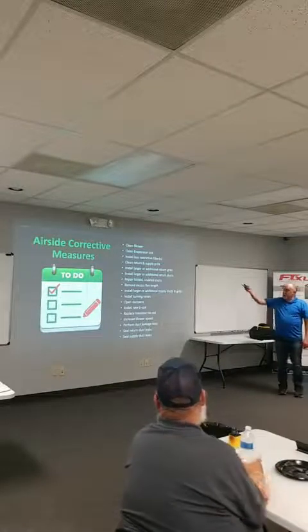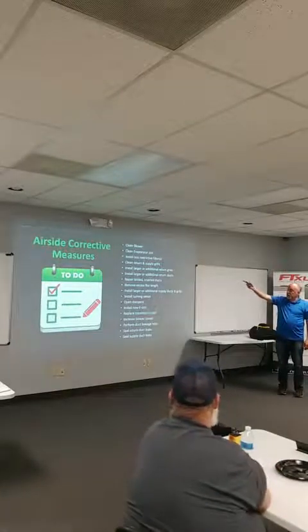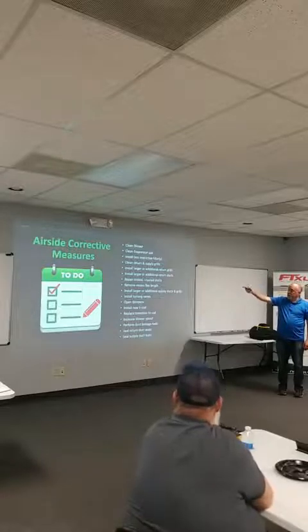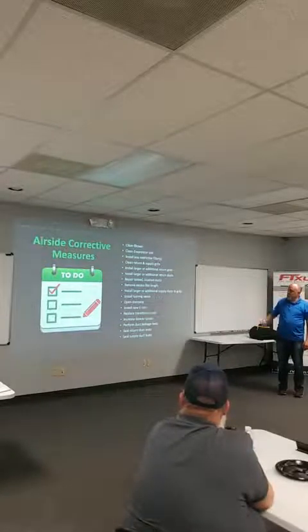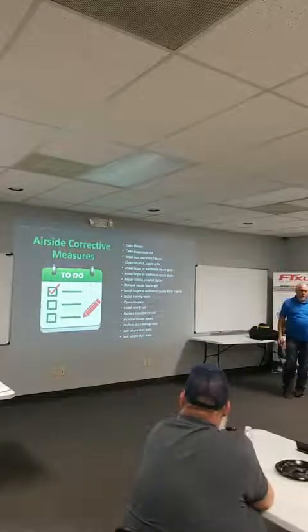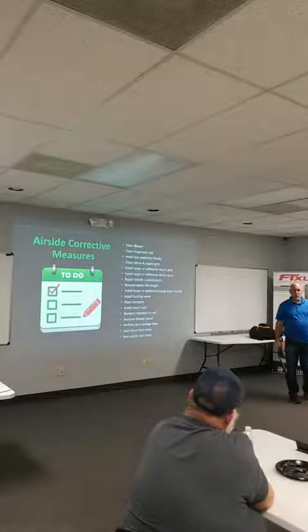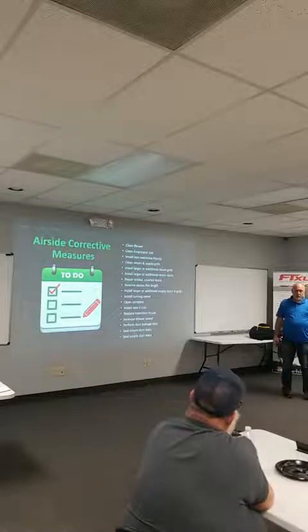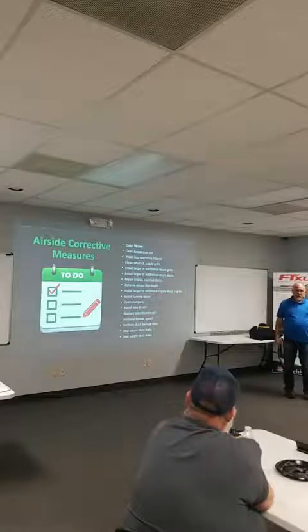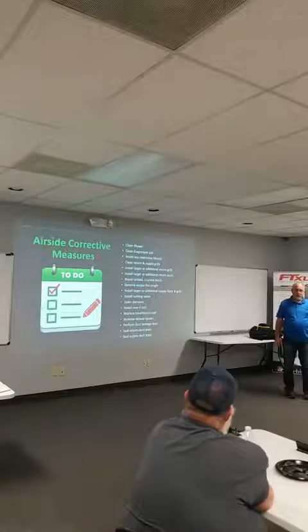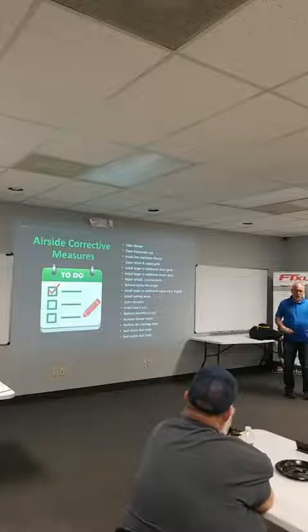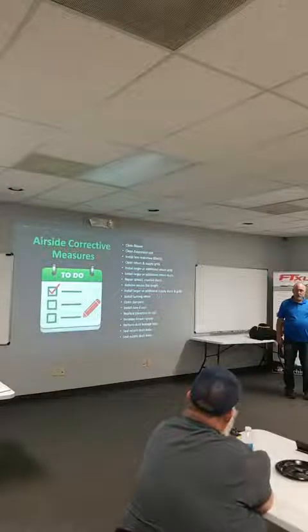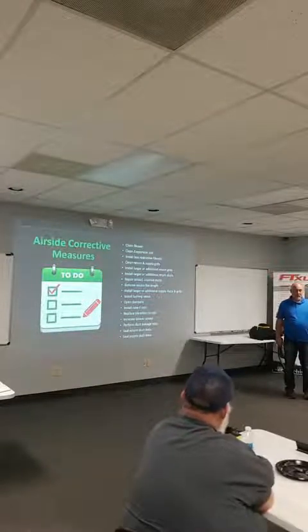So air side corrective measures, we need to be looking at things like cleaning the blower, cleaning the evaporator, less restricted filters, supply air grills, additional returns. Got a company in California. They've increased their revenues somewhere between 40 and 60%. One of the number 1 things they do is add additional return air grills and systems. You're gonna find the same thing. Most commercial systems have undersized filter grills, undersized returns, right? And just going in and adding an additional return air in rooms and things like that, getting these rooms balanced, is gonna make a big, big difference.